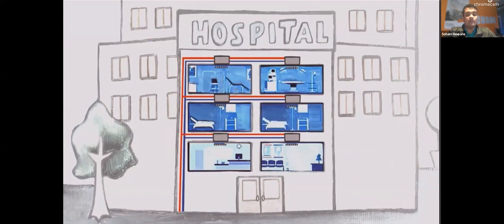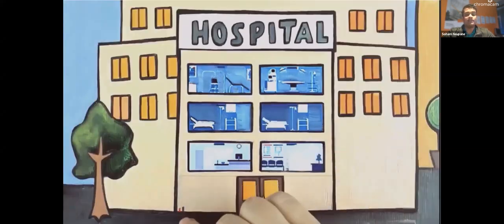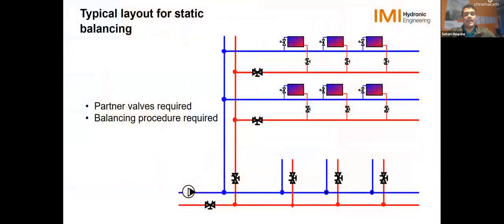Whereas the only thing with manual is it's static. So it's not going to adapt to any pressure changes in your system. It's not reacting to any pressure change in the system. And all it is doing is basically limiting your flow and nothing else. It's setting the max flow limit for the valve. So now when we look at a typical installation in a building, this is how it looks with a manual balancing valve. So you would have a manual balancing valve on each terminal unit, and you would have a manual balancing valve on each branch and a riser and close to the pump as well.